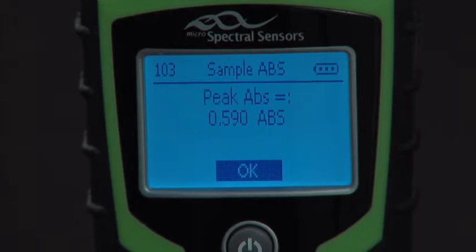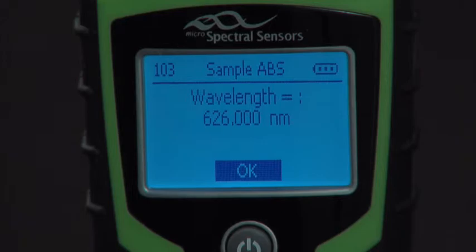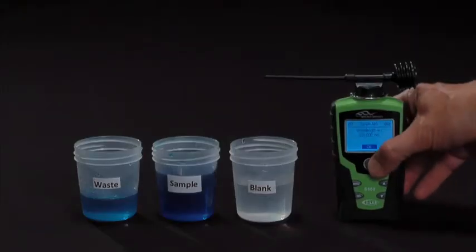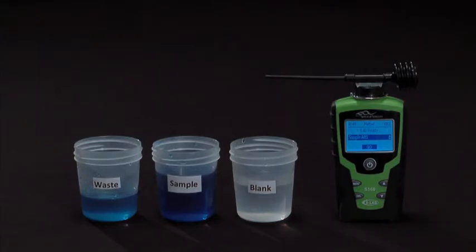Pressing the center button once again, the method will then display the wavelength where the maximum absorbance was observed. We can then press the center button once more. That will end the method, and that's as easy as it is to scan a sample with the iLab.